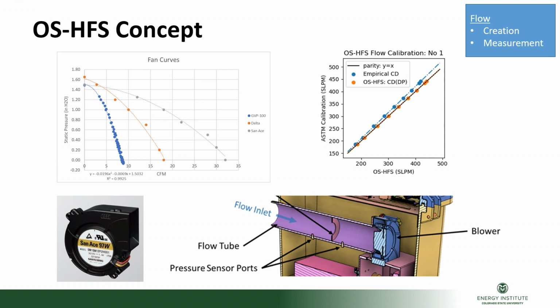With our cataloged empirical discharge coefficient, we did some ASTM dilution calibration, and we saw that we were a little bit off, but pretty close. So we came back in and did our flow rate as a function of pressure differential, and we were able to correct that back to having a really good response.